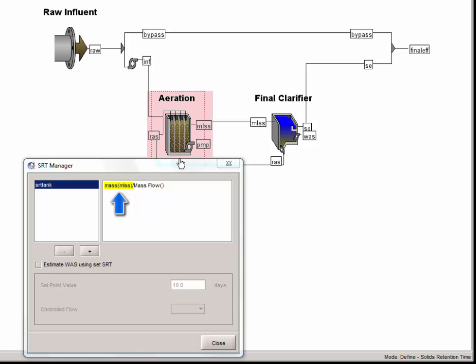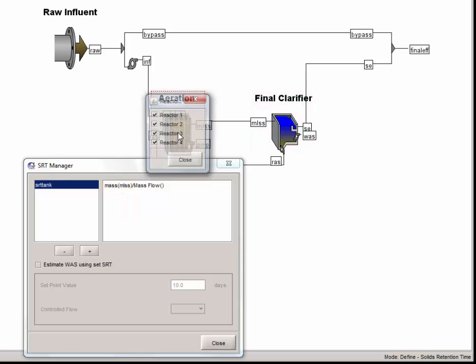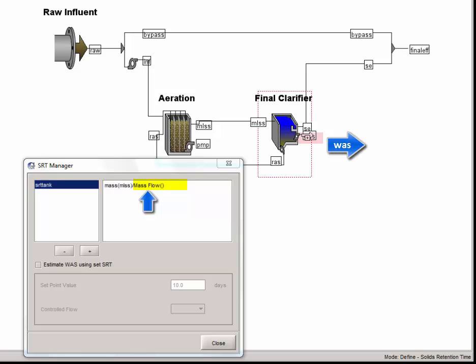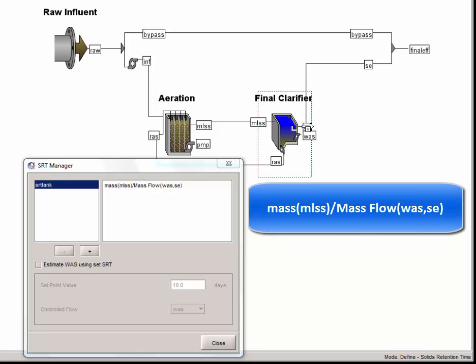Typically, SRT calculations are only concerned with the mass of solids held in the aeration basin. But it is also possible to calculate the SRT using the sum of mass held both in the aeration basin and the final clarifier. To remove terms in the equation, simply click on the associated object on the drawing board. The denominator of the equation is made up of the excess solid mass flow lines used to calculate SRT. Defining the denominator is done by clicking on the flow lines which convey solids out of the system. Typically this will only include the waste flow line, WAS, but for this tutorial we will also include the solids flux in the clarifier effluent stream, SE. This will be the SRT equation we will use for this tutorial.